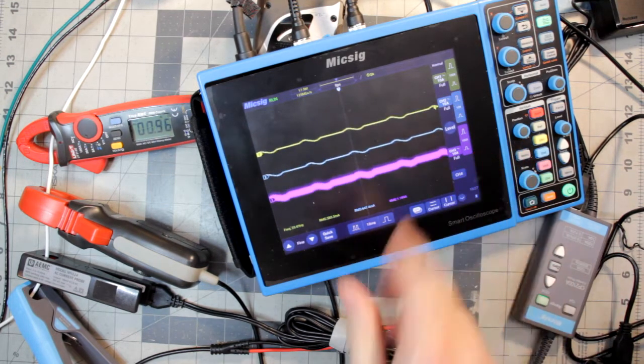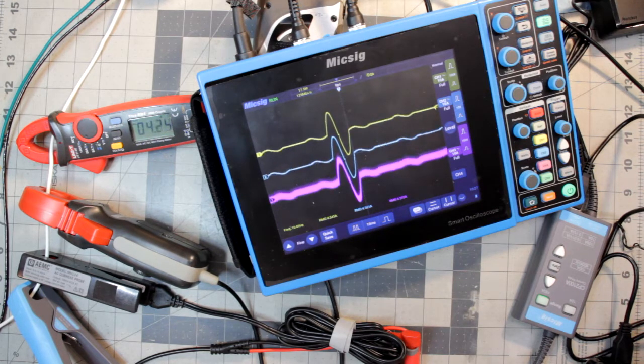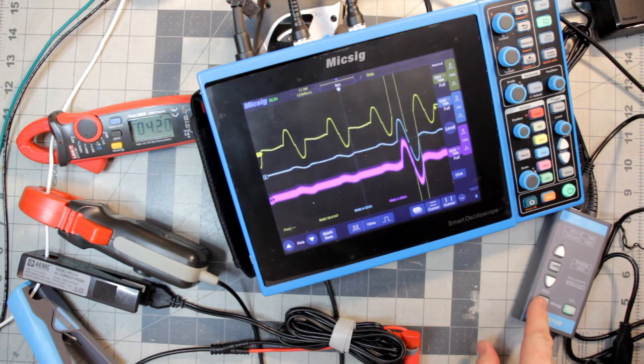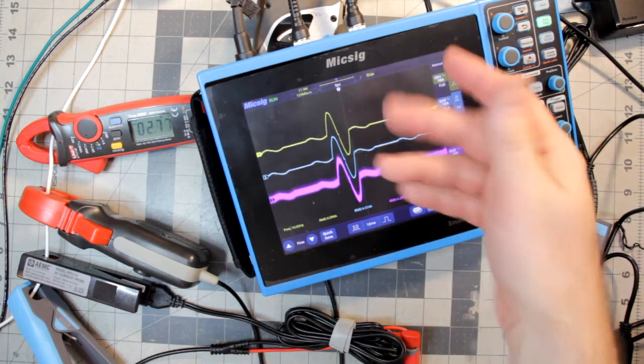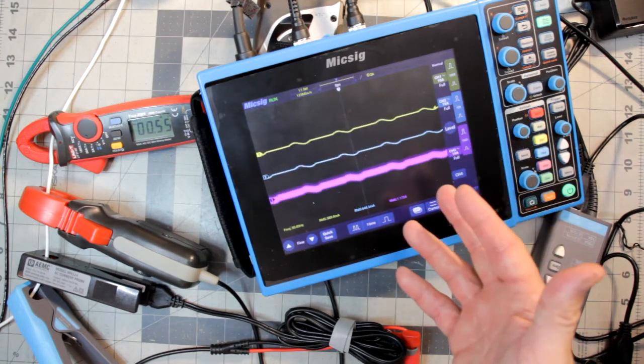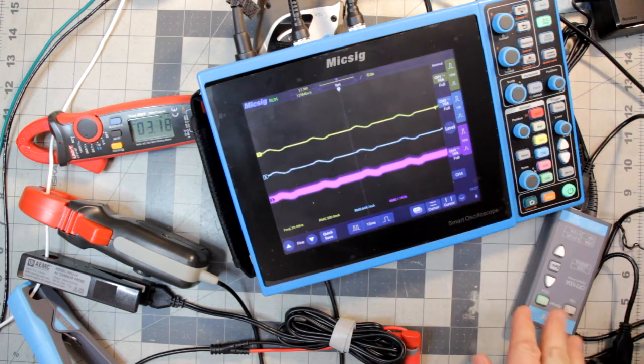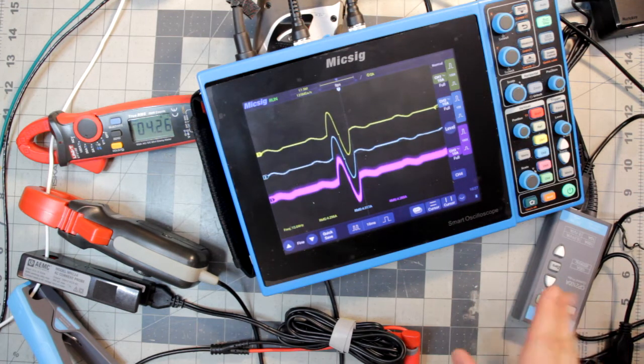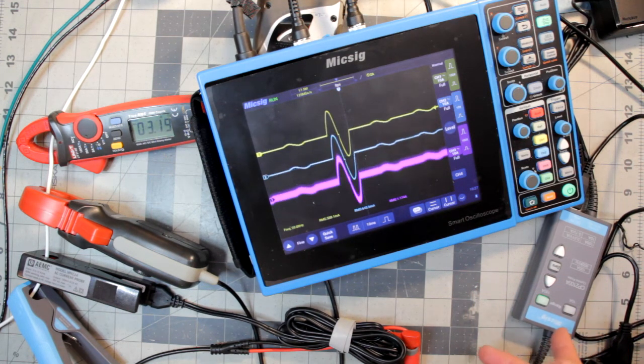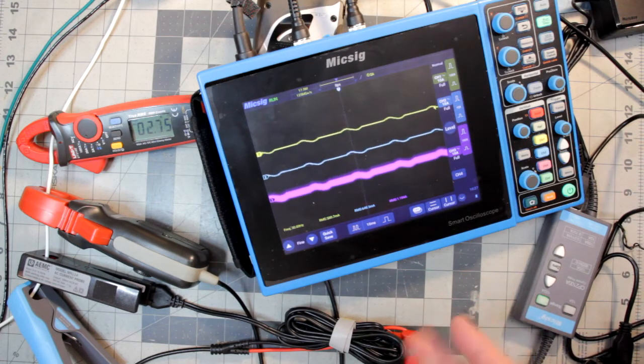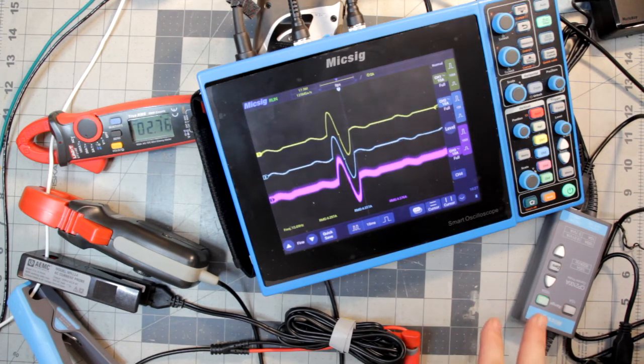Now it takes some futzing to get the settings right. I've got the Micsig set in 100 amp mode. If I tried 10 amp mode before, I think I had problems with it. What'll happen is there are transient spikes occurring that aren't part of RMS, and it'll exceed the range of the Micsig and switch into warning mode. It'll start beeping, meaning this is exceeding the chosen range you have. That's why I have it set to 100 amp mode, but running RMS, it'll pick everything up pretty well.